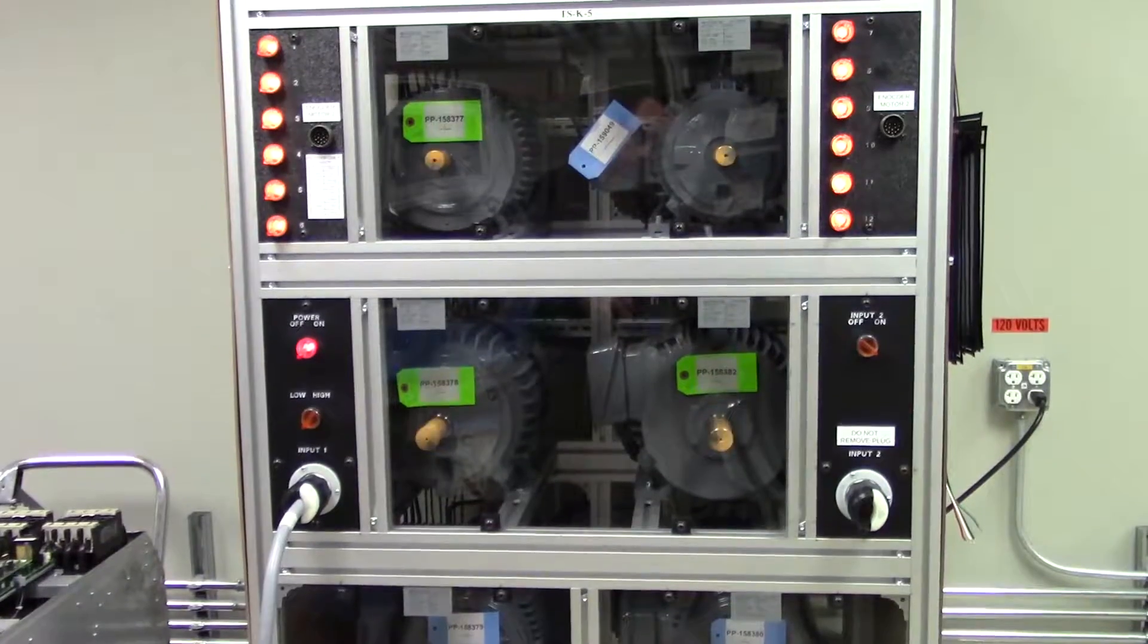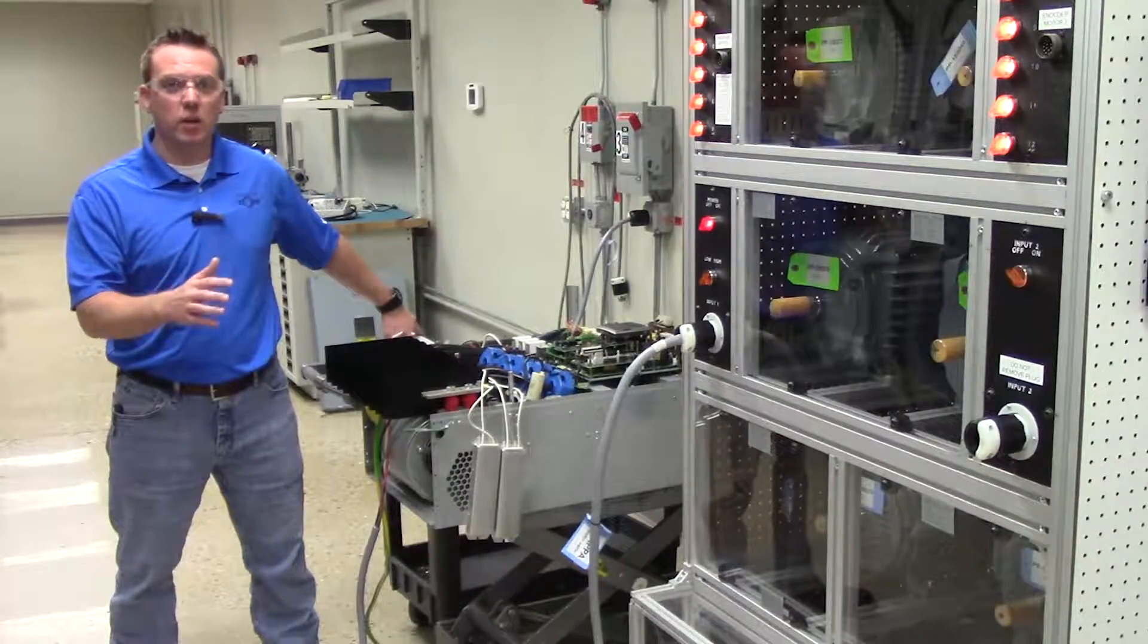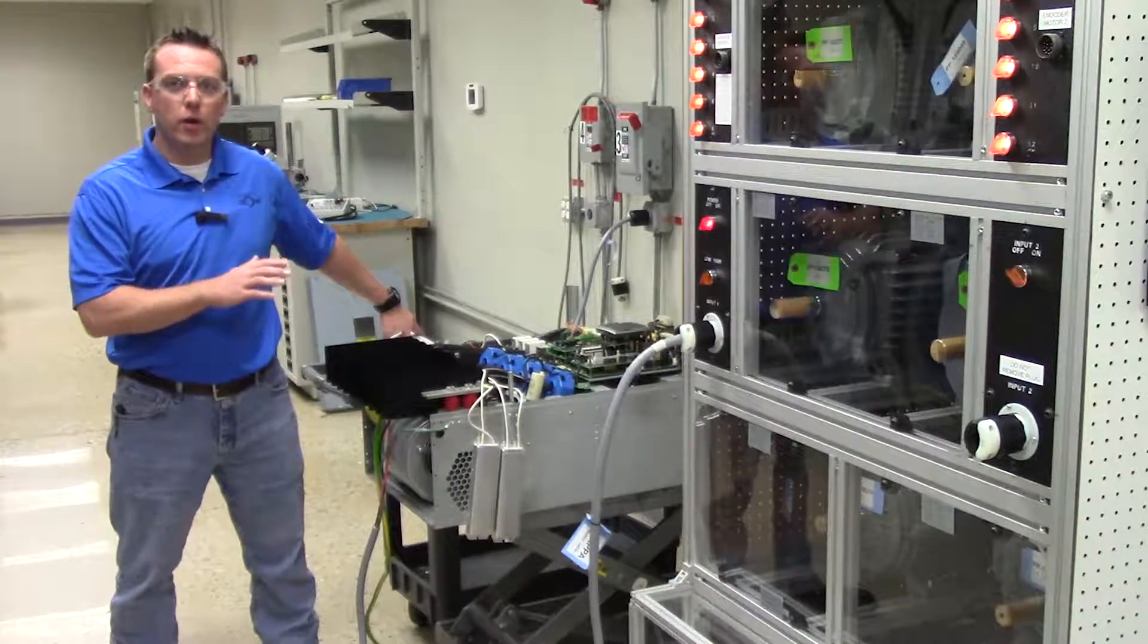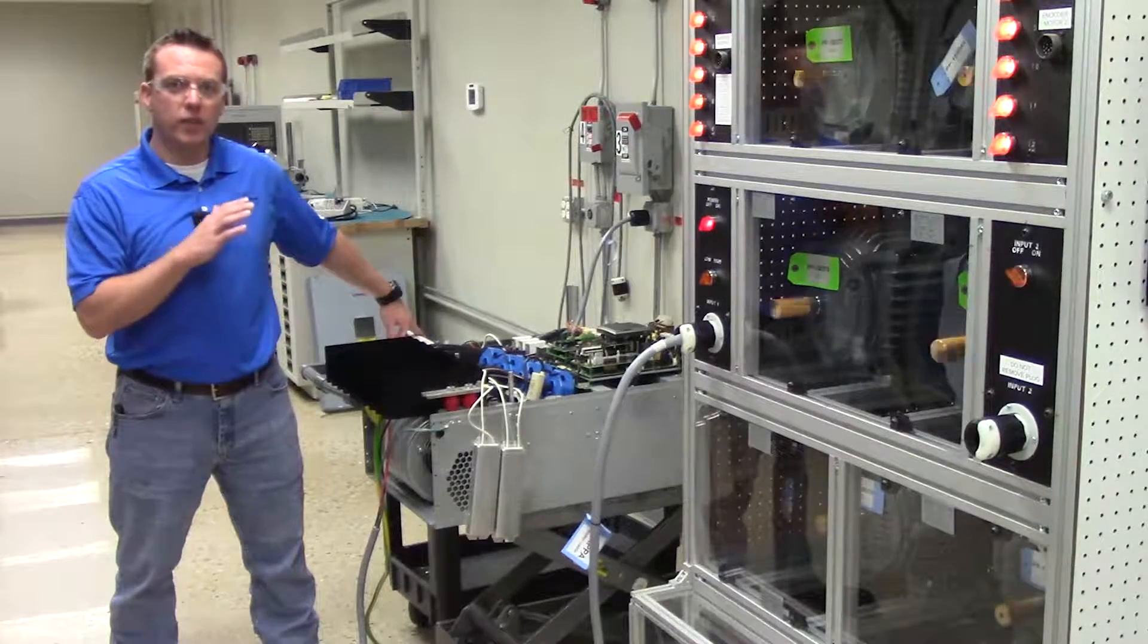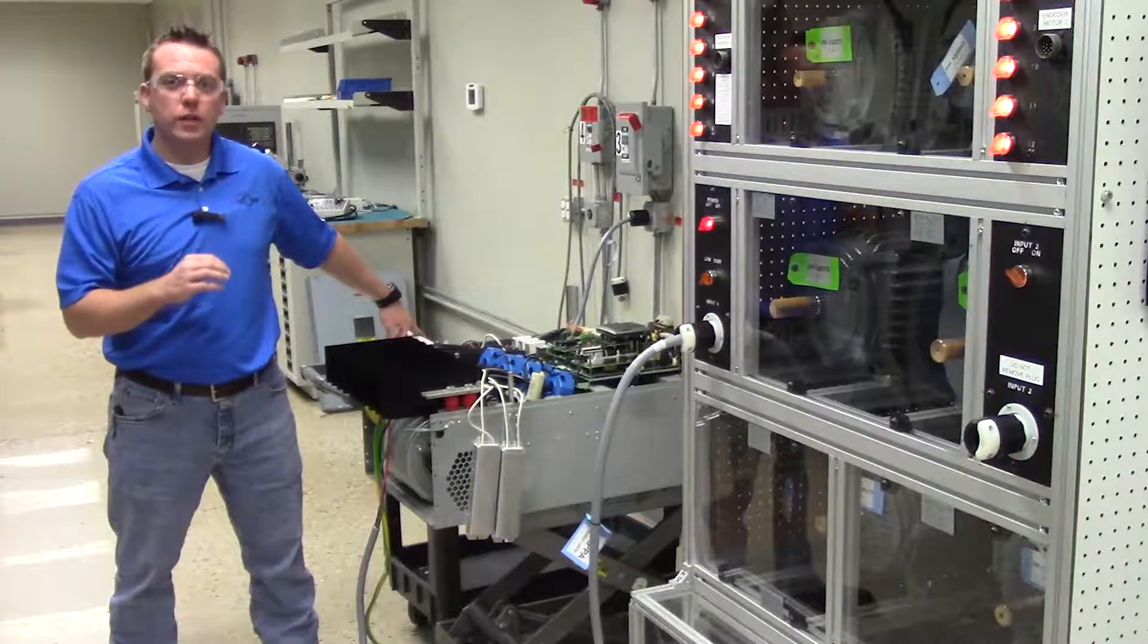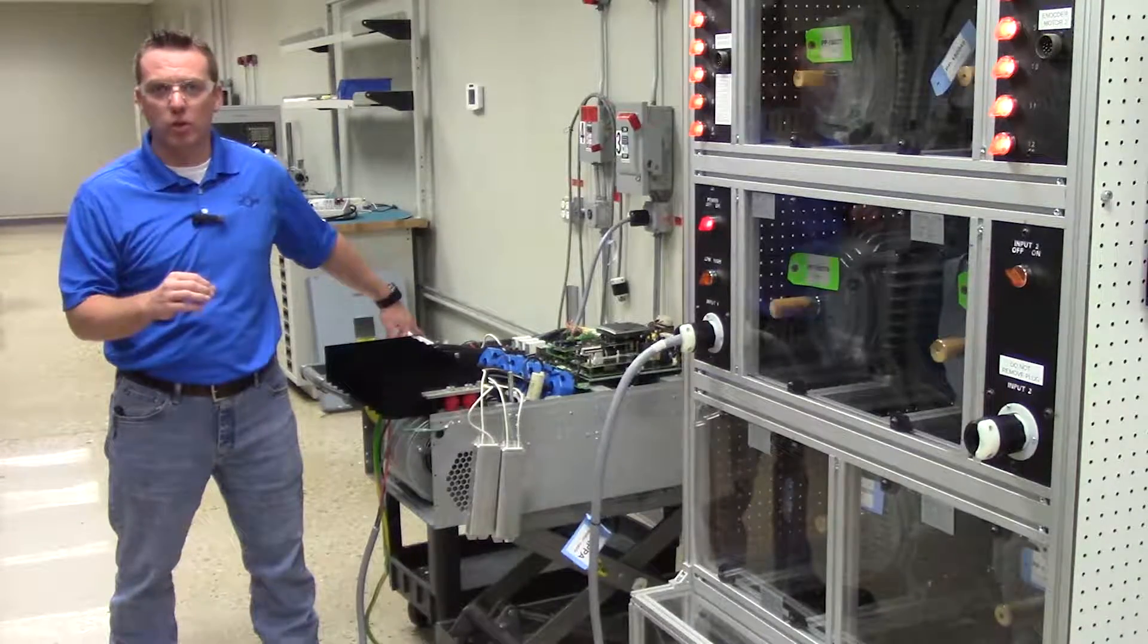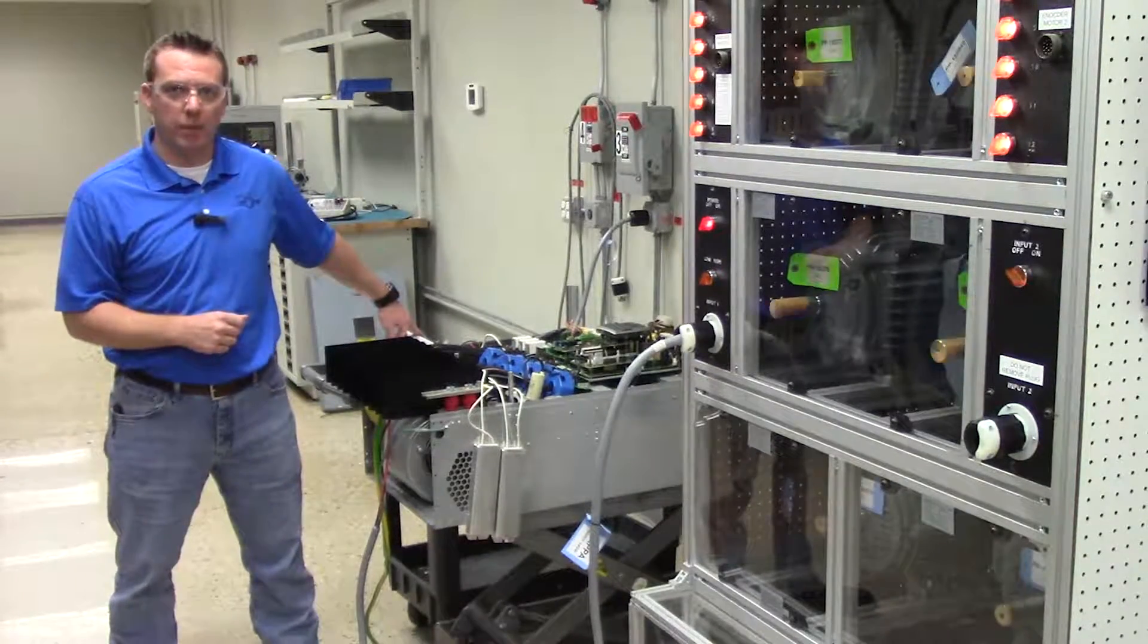So, as you can see, there is enough motor here to simulate the full 130 kilowatts that this drive can output to ensure that the drive will perform as it's supposed to when you install it in your application.